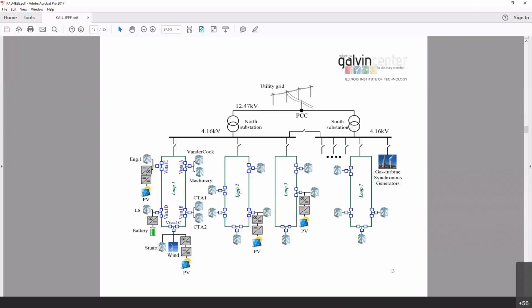These are the individual loops. Each loop has its own building with its own solar PV generation. These are the Vista switches, forming a loop. The good thing about the loop is that if part of the system is not functional, for instance if this cable is broken, I can still feed the building from the other side, so we never lose power using this model.